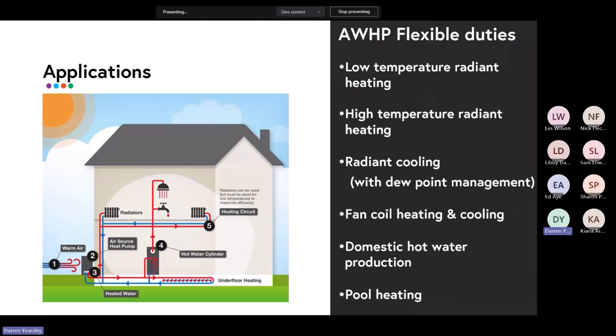It means that you can have an underfloor heating system which works in cooling mode, and we can deliver about 25 to 30 watts of cooling to the space. In terms of comfort, it's a very big increase over a solely air-based system, and it's much more efficient than doing an air-based system. So we've done a few repowers where we've had underfloor heating systems driven from gas boilers, and we've replaced the gas boiler with an array of heat pumps and the right control pack, and then you can have that existing floor system which now does heating and cooling. So that's available as well. We also do fan coils, and then of course domestic hot water production, which I've alluded to quite a bit through this presentation, and pool heating as well.